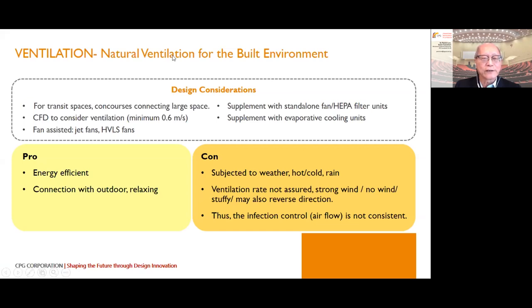How about natural ventilation? It is energy efficient, but subject to weather—sometimes there may be no wind, and sometimes the wind can reverse direction. For natural ventilation, useful for transit spaces, concourses, etc., we conduct computer simulations using prevalent normal air directions to check airflow in naturally ventilated areas. We may add jet fans, big ass fans to assist natural ventilation, HEPA filter units at certain locations, and even evaporative cooling units, which we see quite often nowadays in places like food courts.